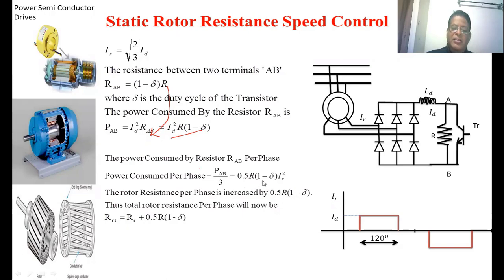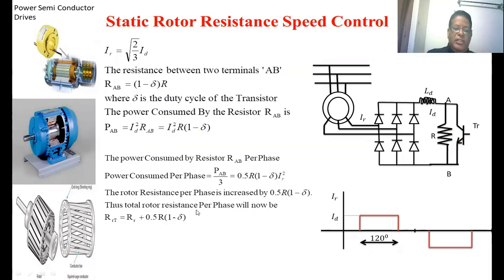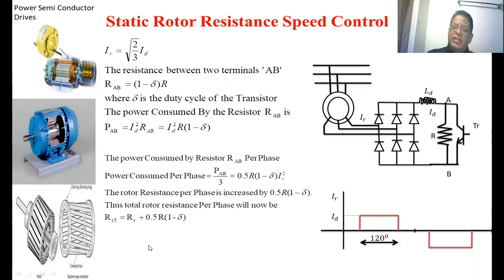This quantity is nothing but a resistance. The total rotor resistance per phase is given as follows. Suppose the rotor resistance per phase is RR. This is the added resistance due to the circuit, where delta is the duty cycle of the BJT. The total resistance per phase is RRP equal to RR plus 0.5R times (1 minus delta). Suppose if the delta value is 0, then the maximum resistance is RR plus 0.5R. So by changing delta, we can vary the resistance from RR to RR plus 0.5R.